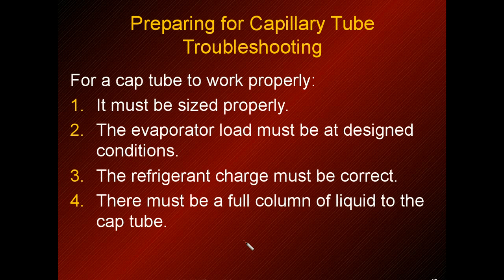For a cap tube system to work, it must be sized properly and the evaporator load must be at design conditions. Remember, it's only designed to maintain the temperature of product removed from a walk-in cooler and placed there for use throughout the day. Refrigerant charge is critical — in such a small system with so little refrigerant, it's easy for the charge to be off. There must also be a full column of liquid to the cap tube.